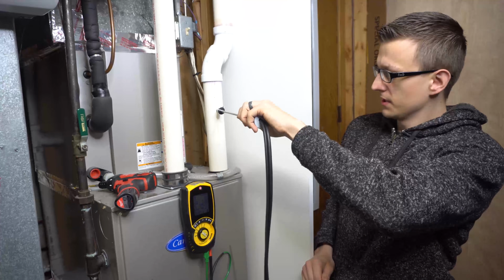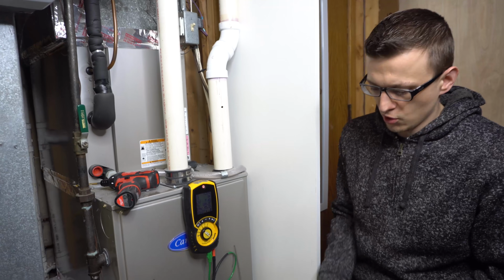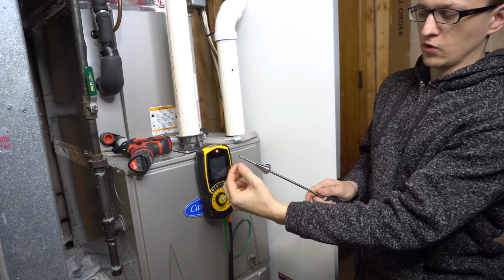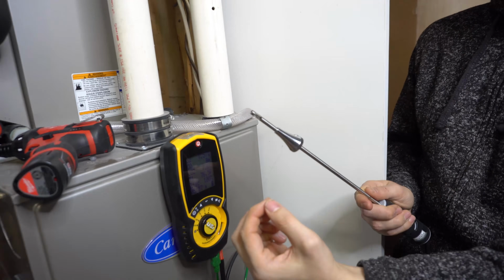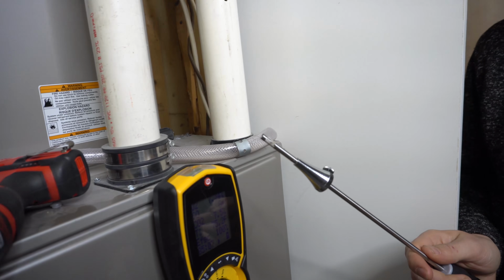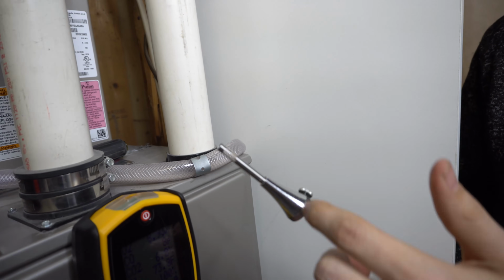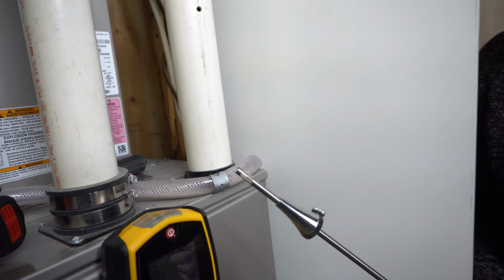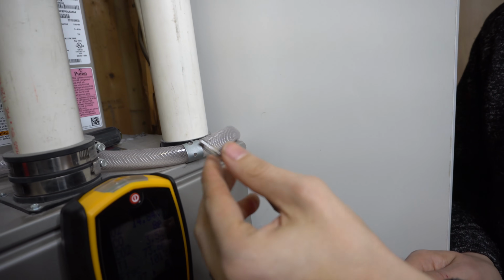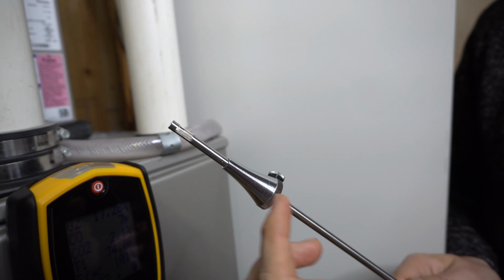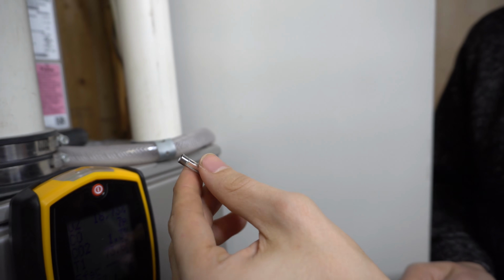Okay, so we're done here. Let's take out my probe. And be careful about grabbing the tip of it, especially if you're measuring this on an 80% furnace, because this will be super hot. Granted, from a high efficiency furnace, it only got to 120 degrees, so it's not too hot. But if you're measuring it on a low efficiency furnace, you will burn yourself if you grab this.